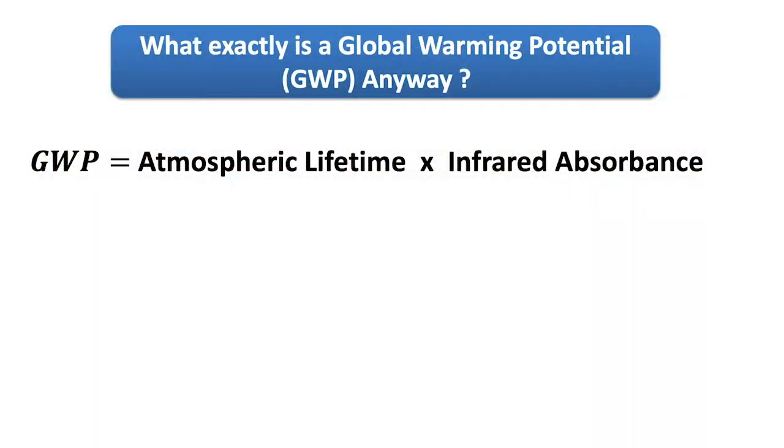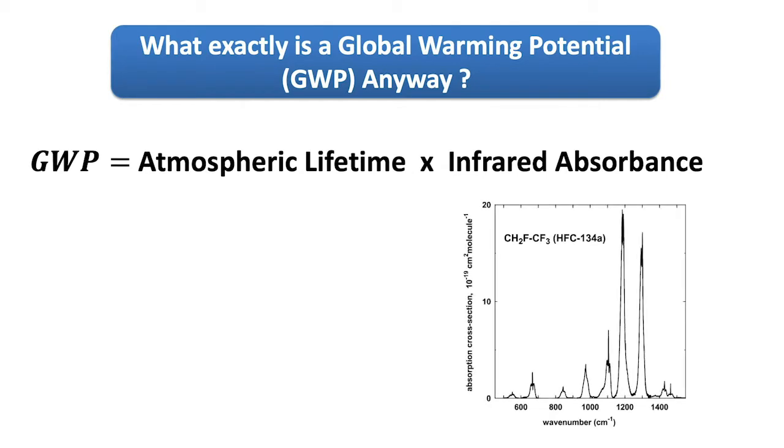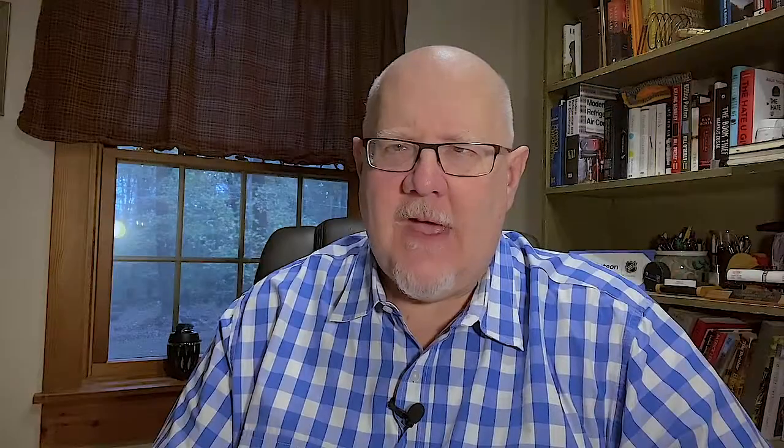Looking at how those GWP numbers are calculated, they use pretty sophisticated atmospheric modeling these days. There are really two factors that determine the GWP value. One is its infrared absorption cross section — a measure of how effective a molecule is at trapping heat, which depends on the atoms and chemical bonds in the molecule. For most refrigerants we've been using over the past several decades, those don't vary a lot. But the other part of the equation is the atmospheric lifetime, which can vary quite a bit — from very short to quite long — and that really determines whether your GWP is high, somewhere in the middle, or very low.